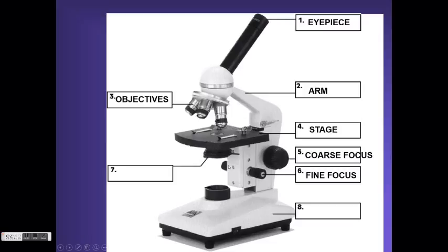We always start with the stage all the way down as far as it can possibly go, because then we know the only place for that stage to go is up. And it might take a while to get that stage up high enough for that image to come into focus, but we're going to be moving that using the coarse focus knob first. Really raise the stage to a point where we can start to maybe get a better image.